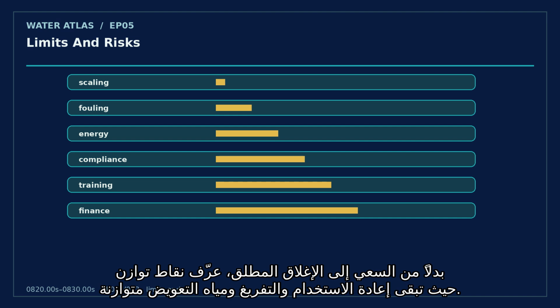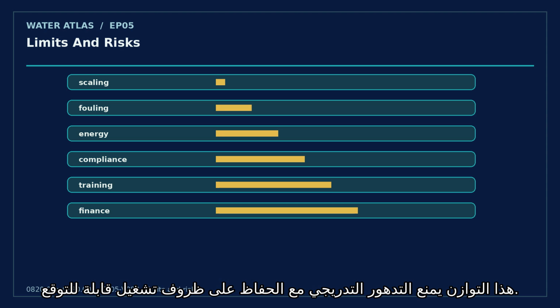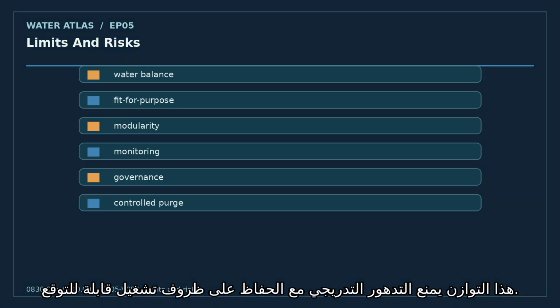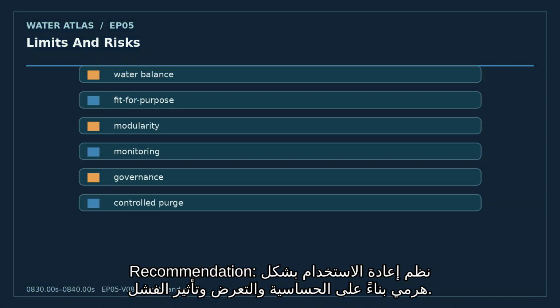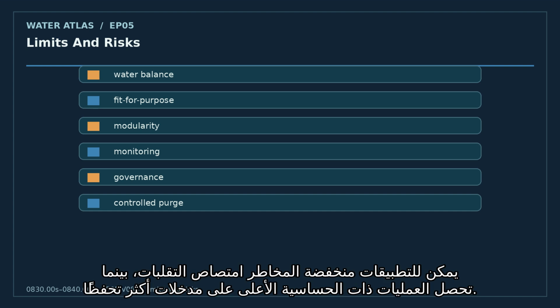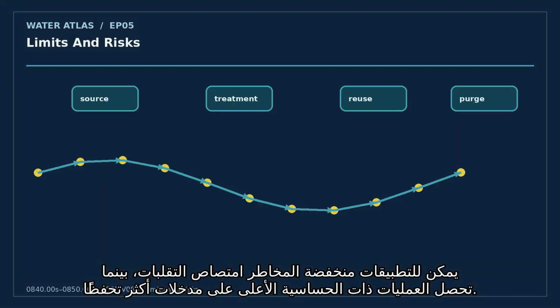This allows decision makers to understand the trade-offs between recovery, energy, and cost. Recommendation: accept that controlled discharge is often necessary to preserve loop integrity. Rather than pursuing absolute closure, define equilibrium points where reuse, purge, and makeup water remain balanced. This balance prevents progressive degradation while maintaining predictable operating conditions.